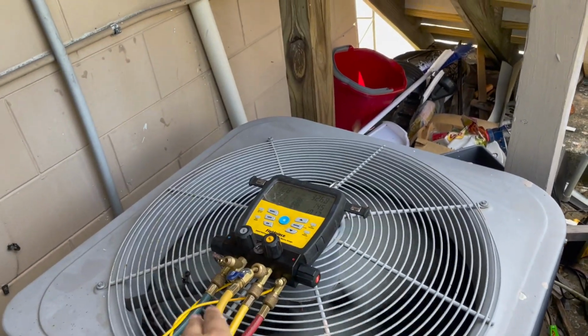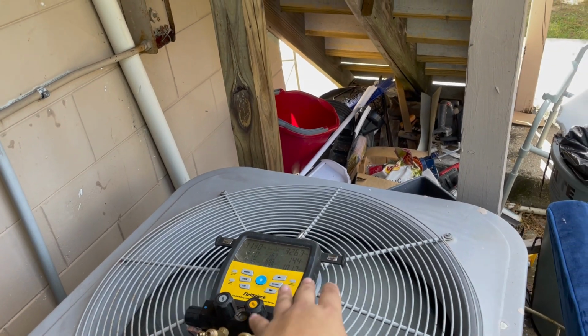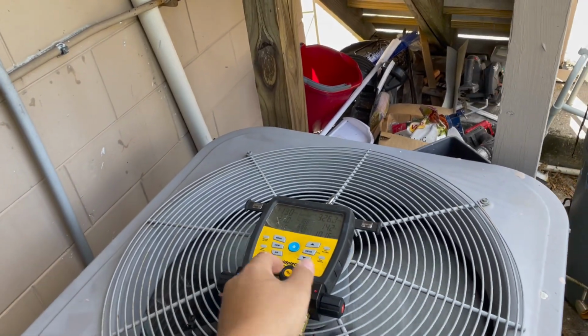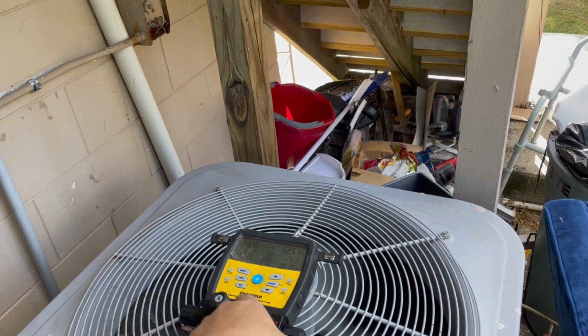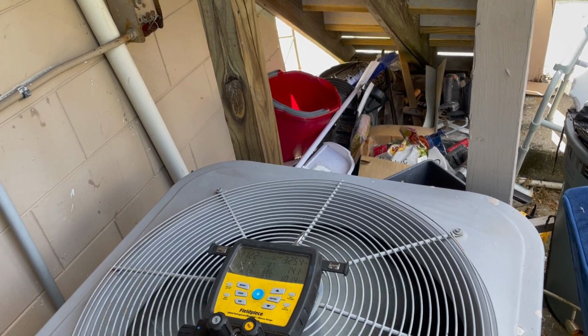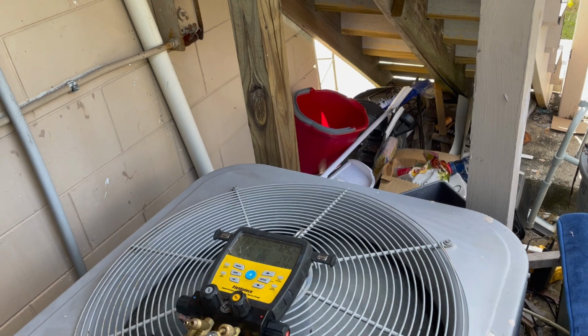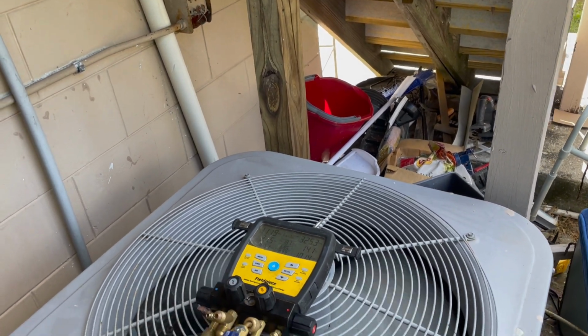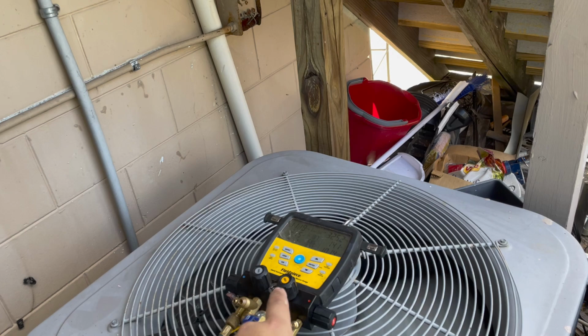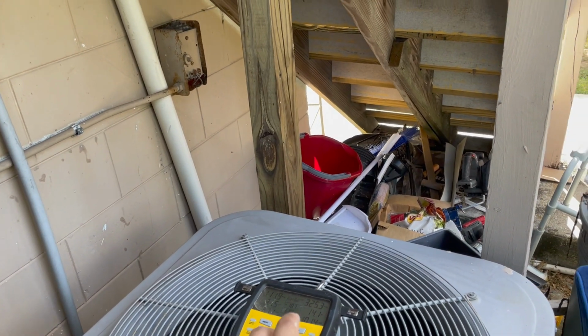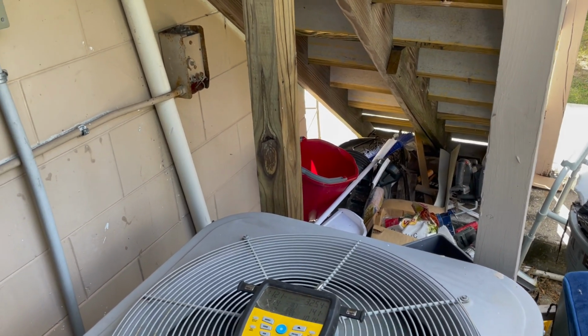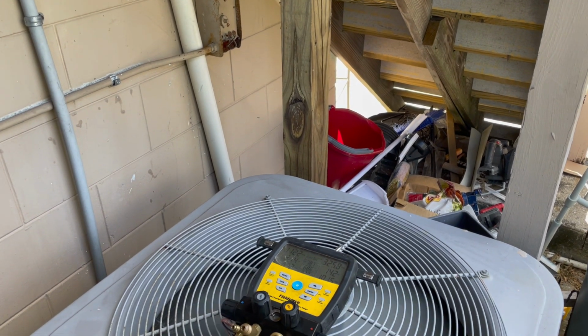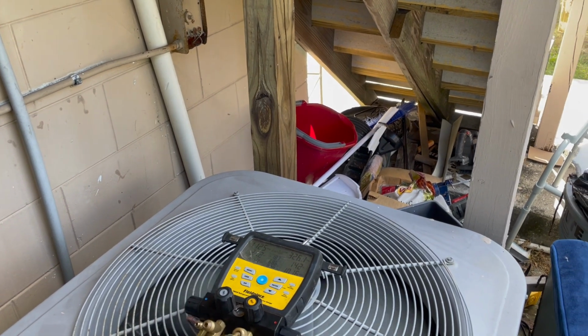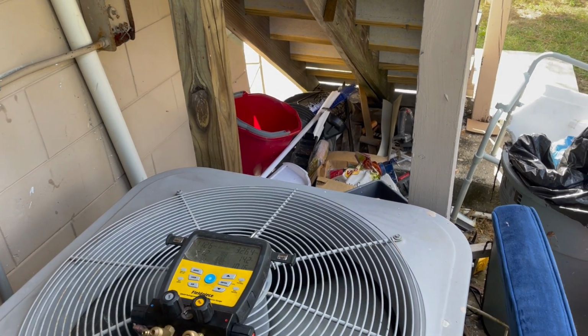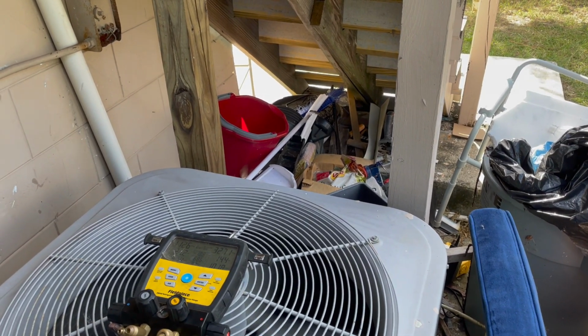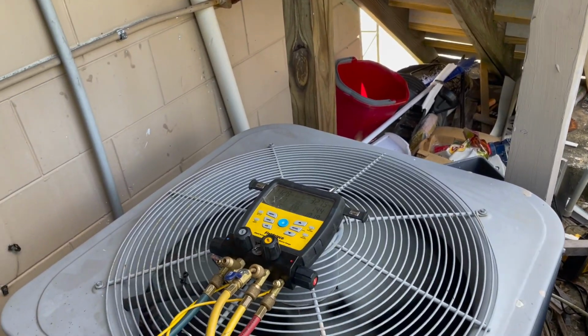Okay, so just about done here. The high side looks exactly the same as I left it. Low side looks a little bit better. It's not freezing anymore. It's almost at 40 degrees saturation, and the superheat's at 30. But like I showed you guys earlier, it looks like he's got a problem with the supply side of his ductwork. He doesn't have enough supply air, it looks like. He doesn't want to do anything about it right now, so I'm just going to finish up by putting in the leak sealer, and then get payment and get out of here.